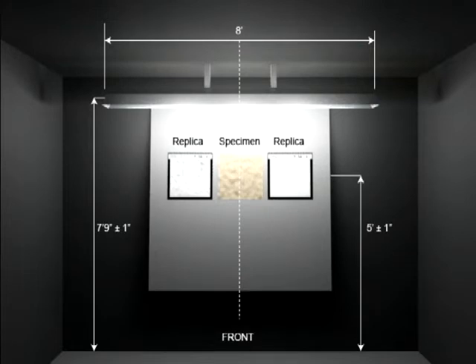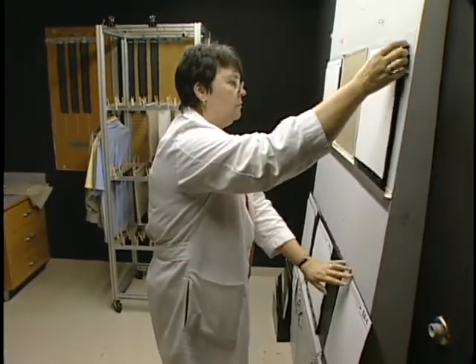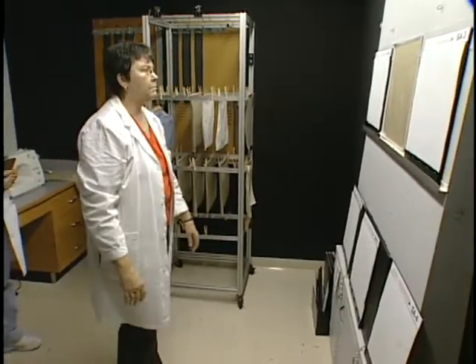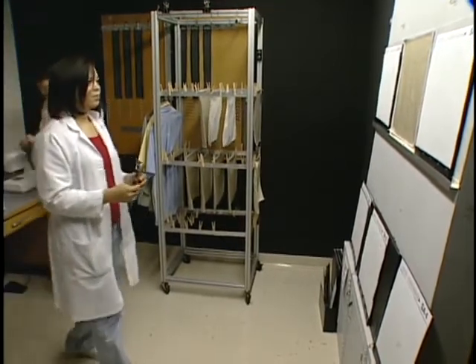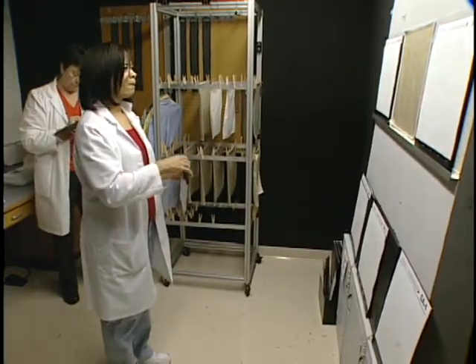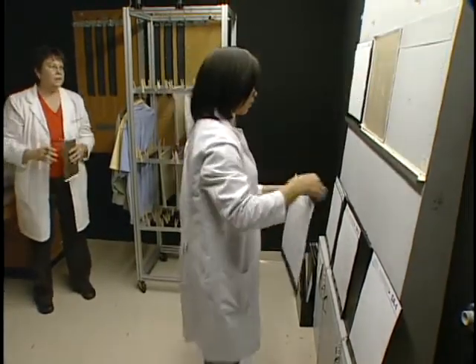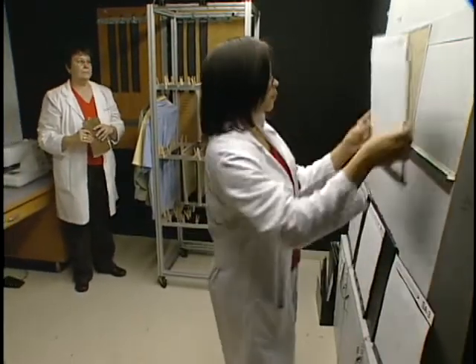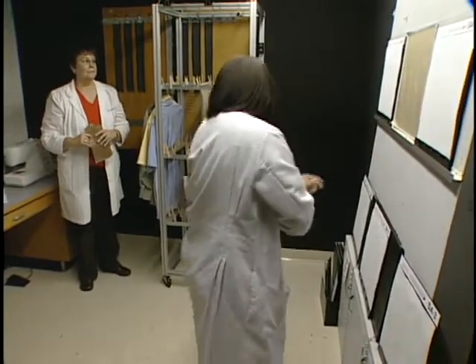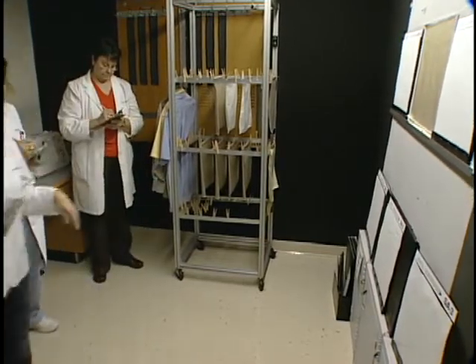The color of the rating board should be painted to match the number 2 gray chip on the AATCC grayscale for staining. Evaluation rooms are preferred. If an evaluation room is not available, the area must be illuminated only with proper overhead lighting. The test method specifies the proper lighting and its location overhead of the viewing board. It is recommended that the side walls be painted a specified matte black, and blackout curtains may be mounted on both sides of the viewing board to eliminate any reflective interference.